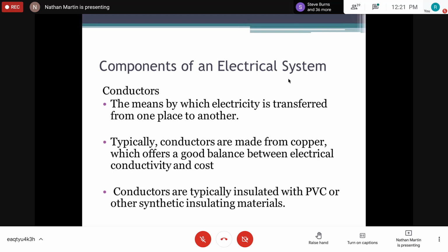The typical temperature range, when we're talking about conductors or cables, is 60 degrees, 75 degrees, and 90 degrees, right? Now, operation of any cable above its stated temperature range will cause that cable to degrade faster than necessary, right? So if you were to operate a 75-degree cable at 90 degrees, and these are in Celsius, then it will start to degrade at a much higher rate, right? And this is why, when we're talking about overloading the cables, remember when you pass a current through a conductor, it will produce heat, right? And if we pass more than the maximum allowable current through that conductor, then the insulation will start to break down, all right? Because it's designed to work at a particular temperature.